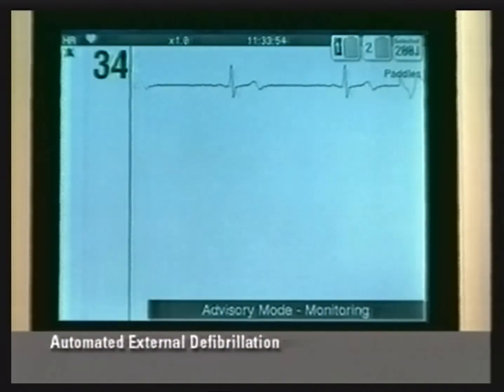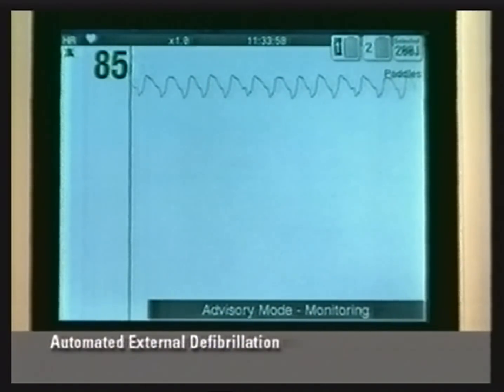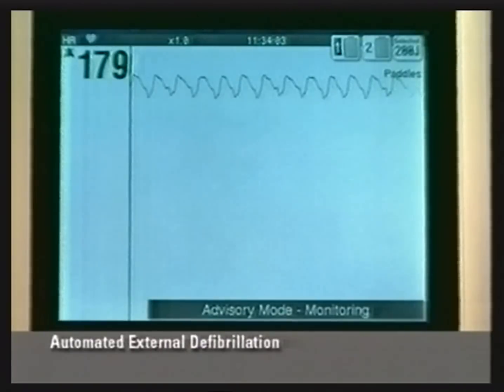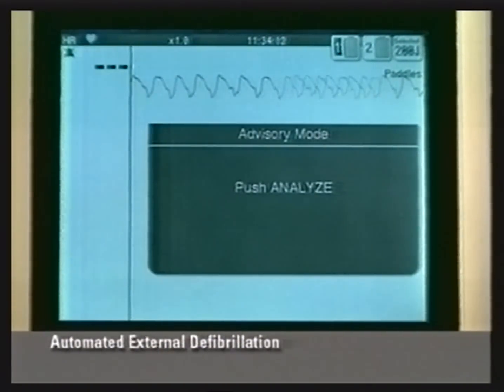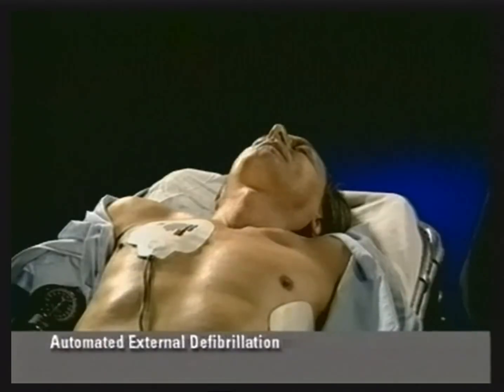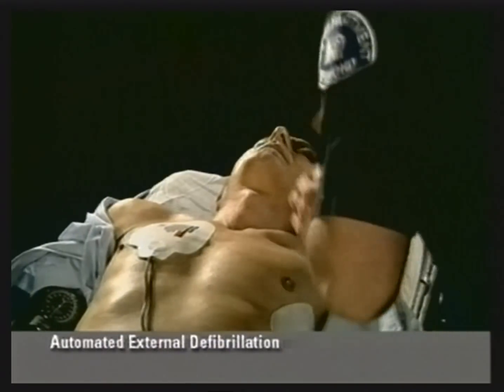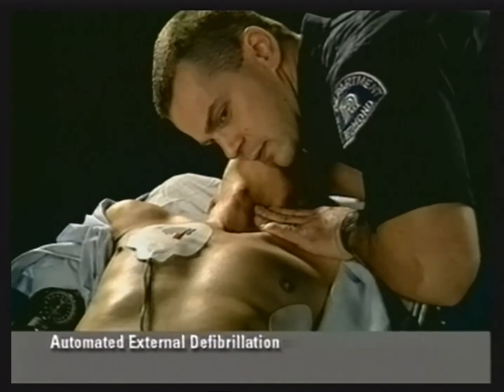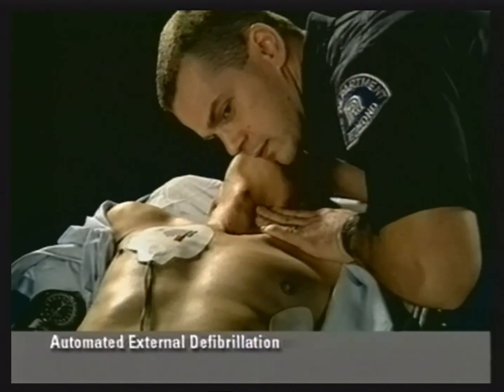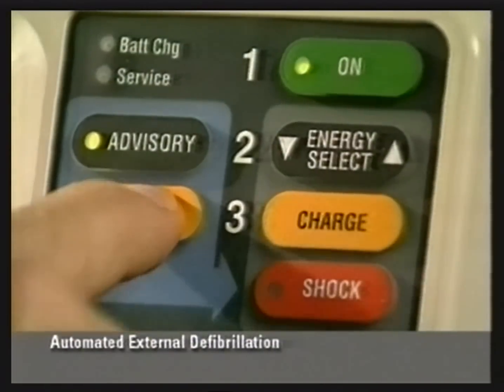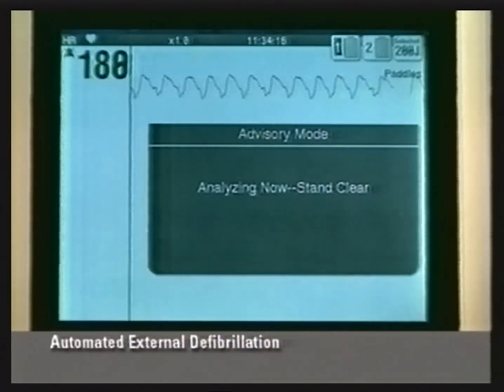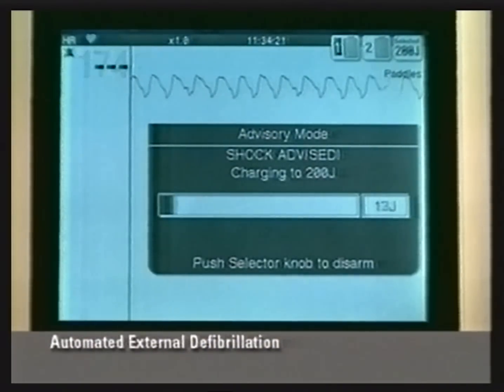When the defibrillator is in advisory mode monitoring, it continuously monitors the ECG for a potentially shockable rhythm. If a potentially shockable rhythm is detected, the defibrillator prompts you to push Analyze. You should confirm the patient is unconscious, pulseless, and not breathing spontaneously, confirm no motion is present, then press Analyze. Analyzing now. Stand clear. Shock advised.